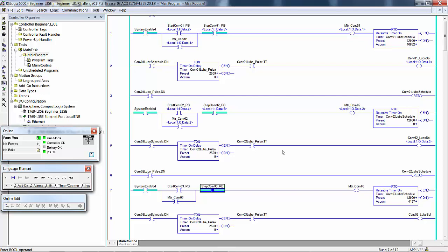We have the rung that actually runs the conveyor, and then we've got the lube solenoid rung, and then we've got a reset for the lube timer. If you still have logic for conveyor 3 that is using bit 3 of the output word, you will see erratic behavior. Now we unaliased that so you shouldn't. If so, you will have to delete the rung or give the output a different tag. You can see that the logic for one is independent of the other. These programs scan top to bottom, left to right.